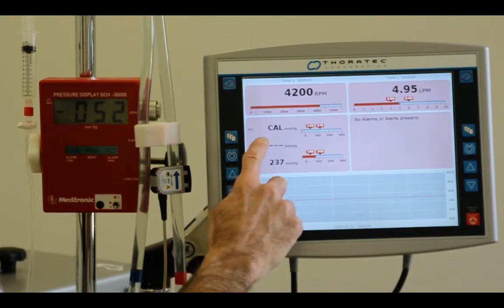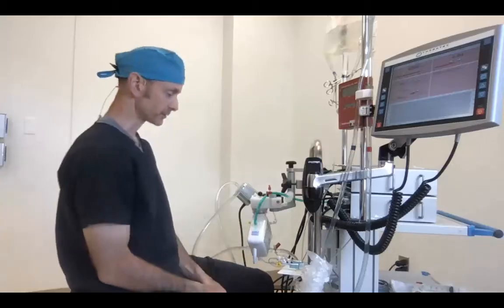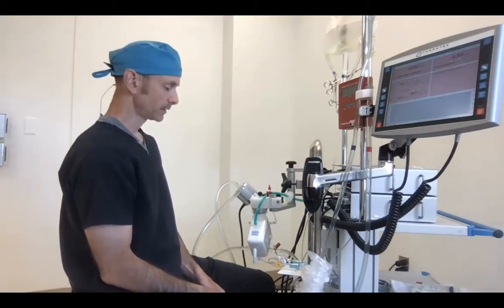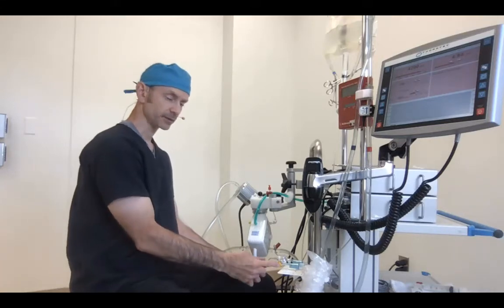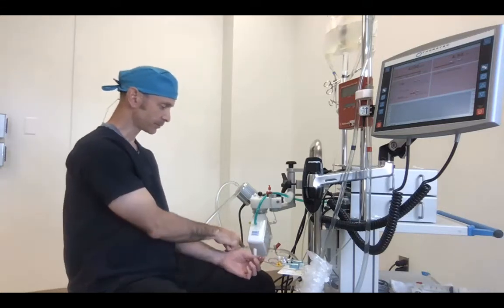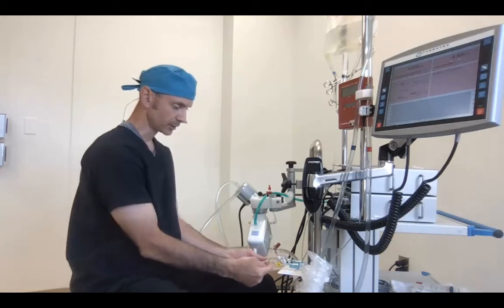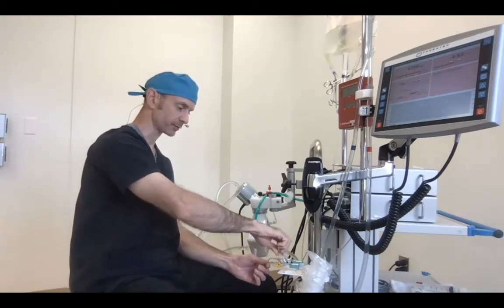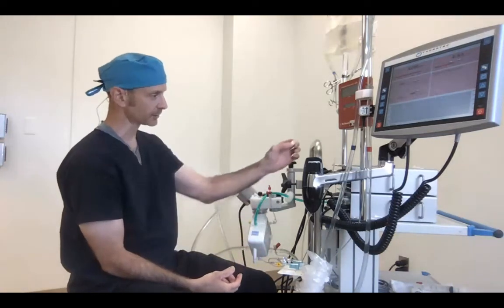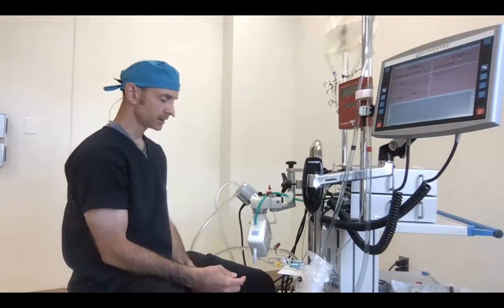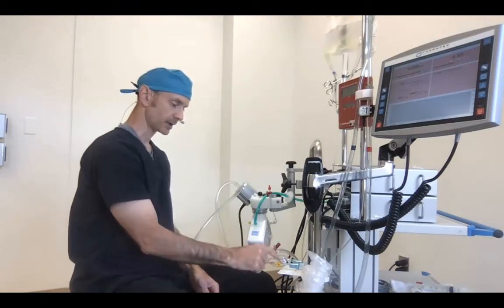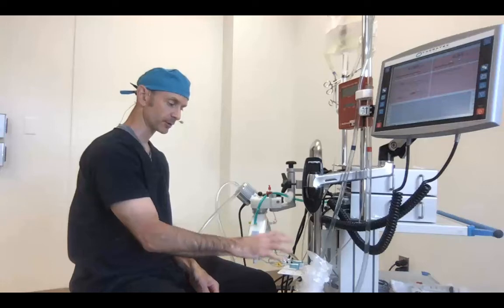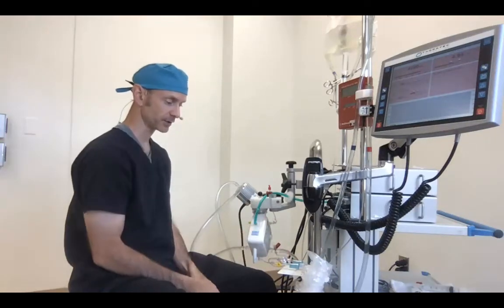Let's go ahead and calibrate our P1 sensor here, just as a reminder of how we do that. First we come down to the transducer. This is P1, which goes to the pre-membrane side. We turn that off to the pressure source and remove the cap, and keep that cap sterile by setting it aside, not letting it touch anything. Now the stopcock is open to air. Atmospheric pressure is what that transducer is feeling.